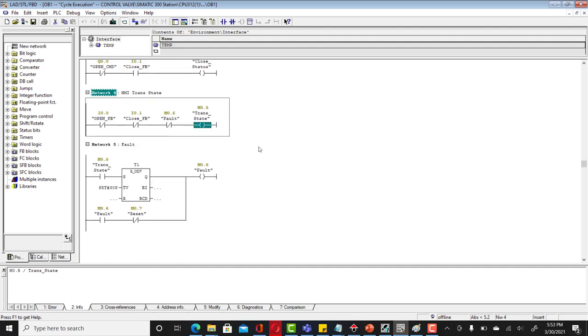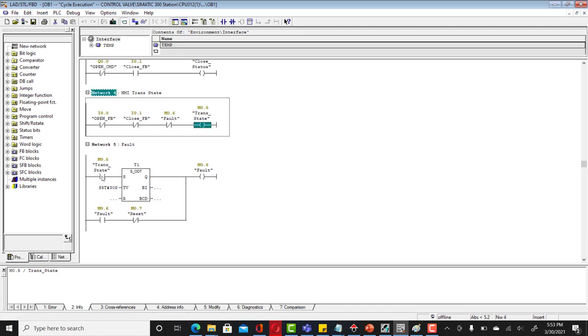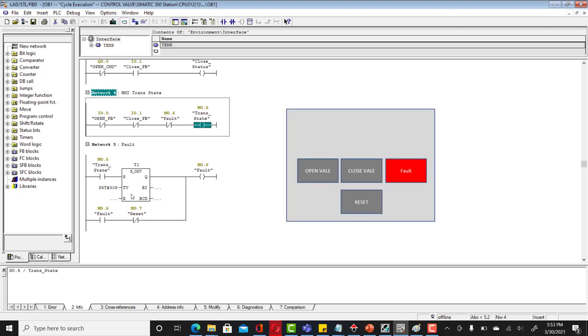For sure you don't want this to be in a transition state forever. If your valve is in a transition state for a longer run, you got that transition signal here and you turn on a timer for 30 seconds. If your valve is in a transition state for 30 seconds after getting a command from operator, then you need to turn on the fault.